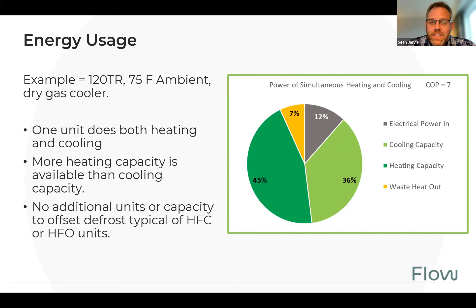Getting a little deeper onto that pressure enthalpy diagram, what's really neat is you can extract high-grade heat and low-grade heat out of the same system. If you don't need that low-grade heat, you adjust your gas cooler temperature. If you need more, you adjust your gas cooler temperature. If you want to be more efficient, you lower your pressure. So you can move this top end all over the place while still holding this bottom end in the chiller constant, which is pretty neat.